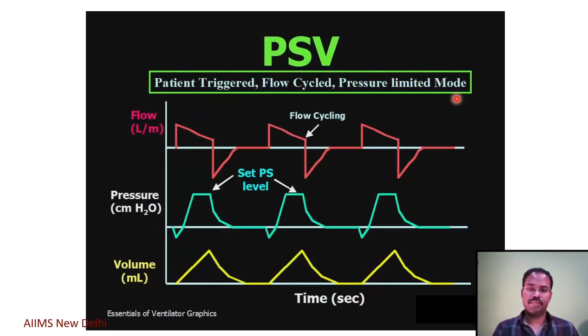However, in PSV mode, there is always a backup ventilation rate. So if the patient does not breathe for a certain period of time on his own, the ventilator will initiate its own breaths, which will be time cycled. As I said, the difference between pressure control and pressure support mode is that in PSV almost always it will be patient triggered breaths, whereas in PCV these are usually time triggered, and both are pressure limited, but PCV is time cycled and the flow reaches the baseline, whereas PSV is flow cycled and flow does not reach the baseline.